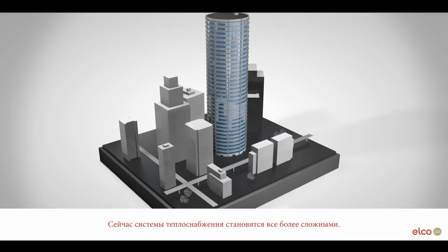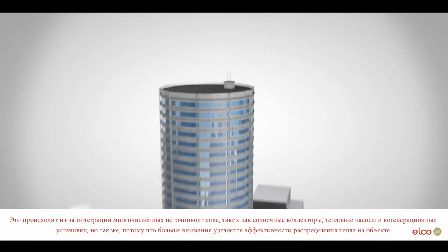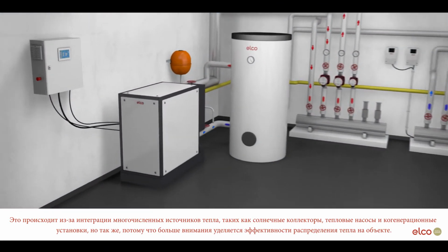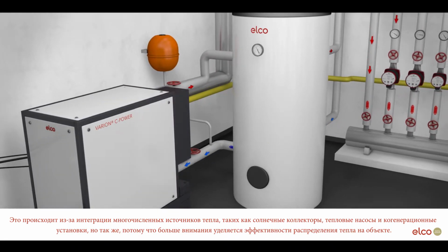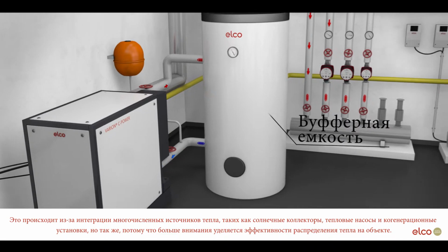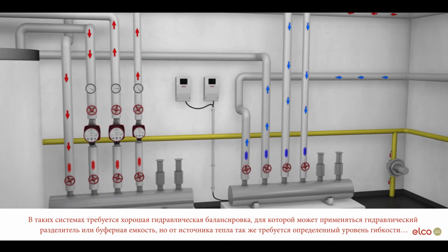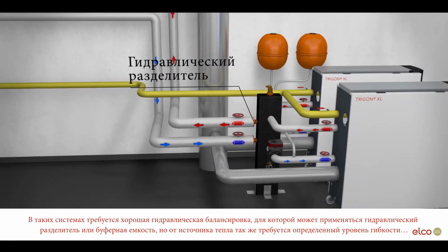Nowadays, heating systems in commercial buildings are becoming more and more complicated. This is due to integration of multiple heat sources, like solar, heat pumps and CHP units, but also because there's more focus on having an efficient heat distribution in the building. This complexity requires proper hydraulic balancing, best done with a low-loss header or buffer, but also demands a certain flexibility and reaction time from the heat sources used.